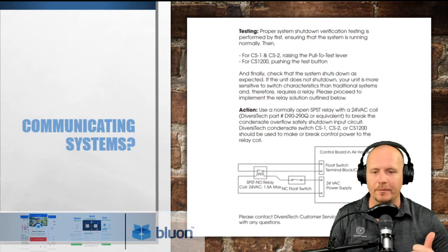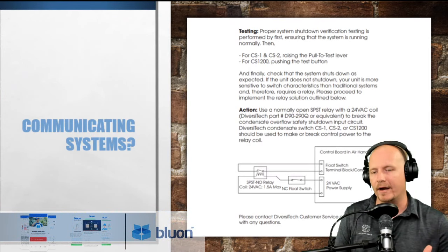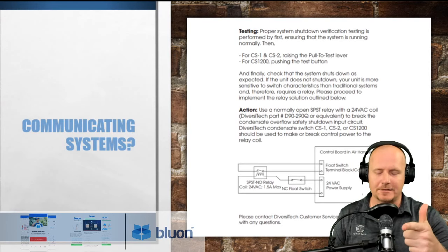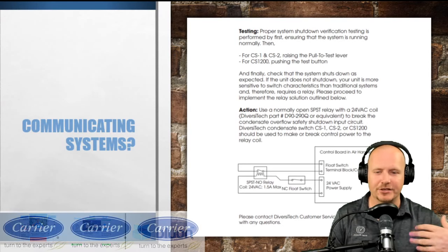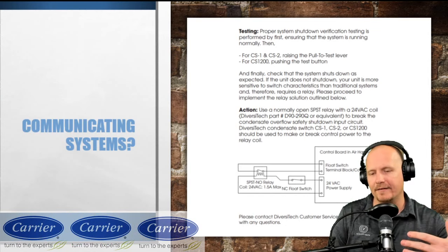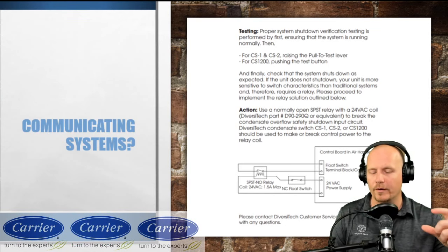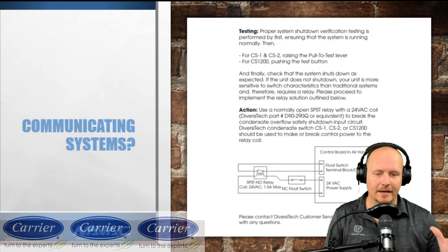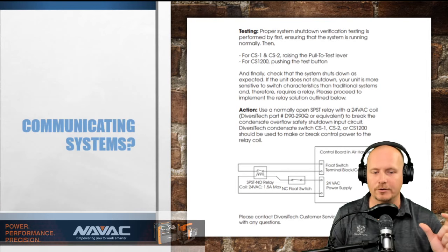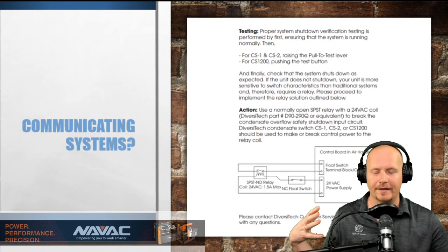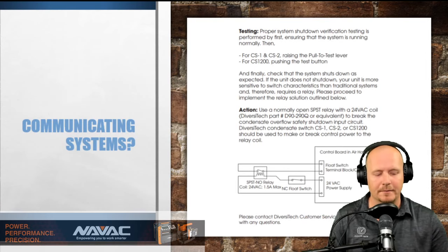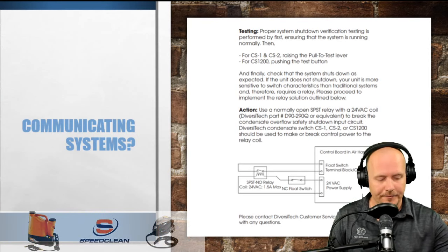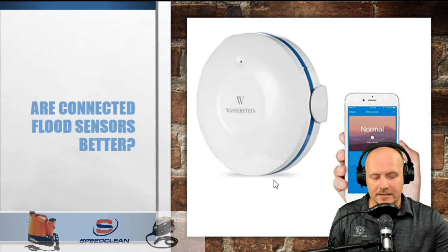And that issue that we've been seeing are cases where float switches are staying stuck closed. Now, that's not specifically with this communicating system thing, but this is just an indication that obviously if it's making and breaking properly with the contacts in a relay and it's not making and breaking with the contacts in the float switch, that those contacts aren't providing that same level of clearance and sort of make and break reliability.